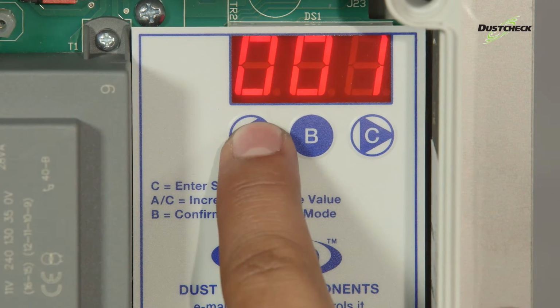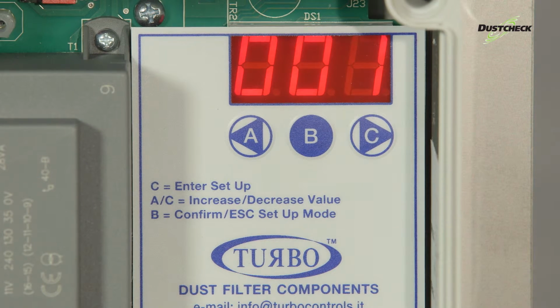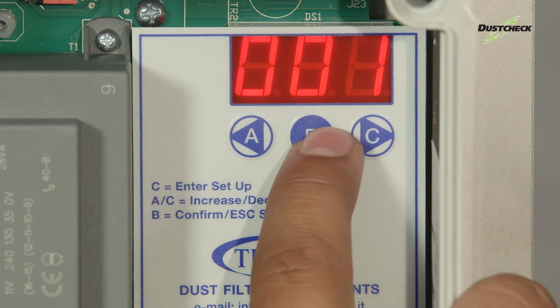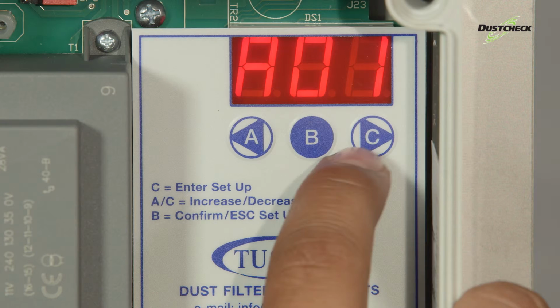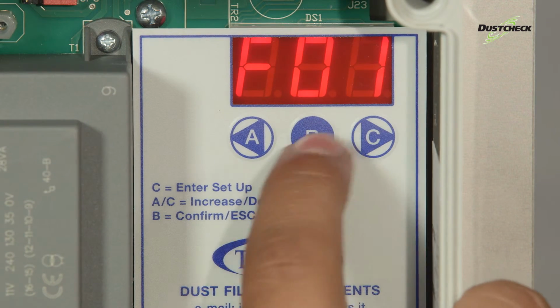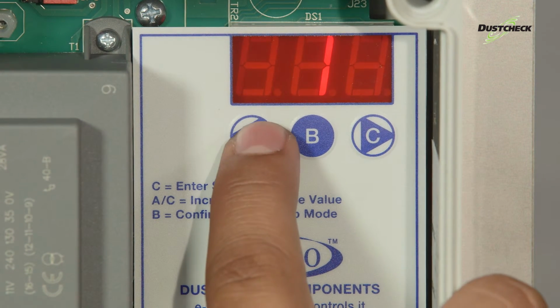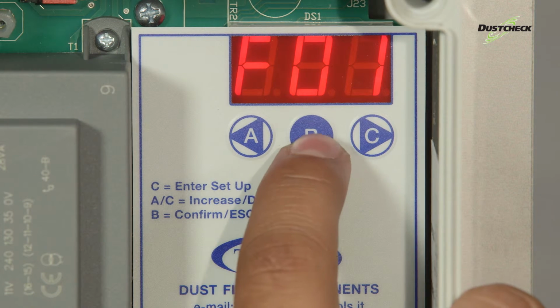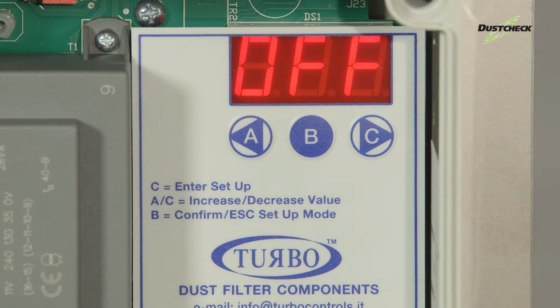F05 provides the facility to have the controller run through a series of cleaning cycles after the air mover has stopped and no airflow exists through the filter unit. If this facility is required, function F01 should also be set to 0, and a connection is required on terminals 12 and 13 to provide the signal.